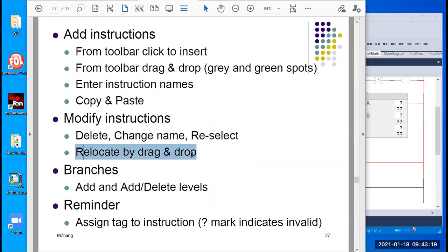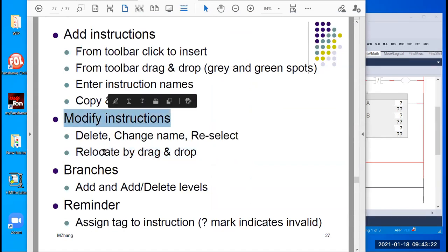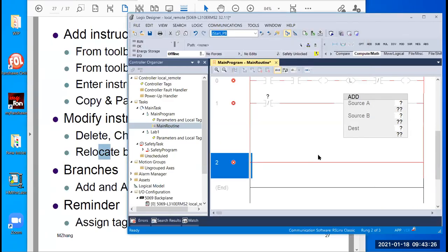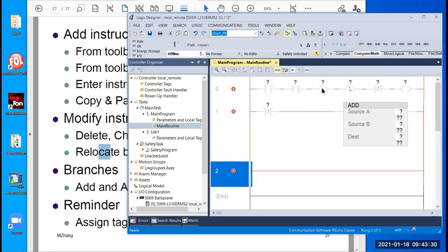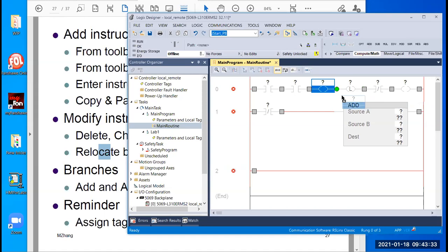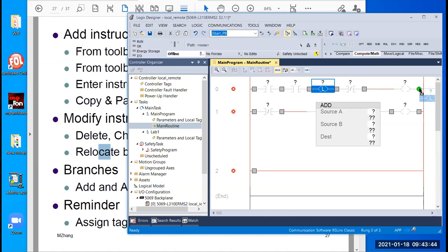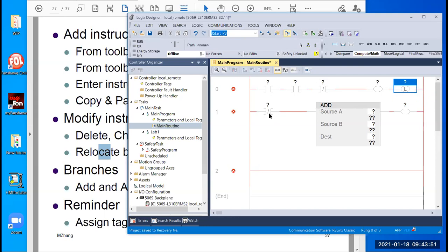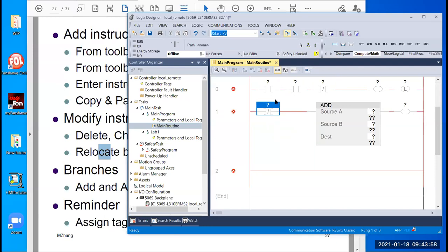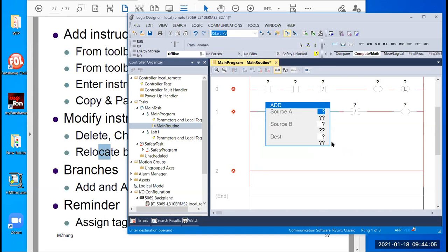You can also relocate instructions — another way to modify. You can relocate by drag and drop. If you want to drag an instruction, you need to click the instruction name itself and then drag it. Pay attention: there are two parts on each element — the instruction and the tag. If you click only the top part you're dragging the tag, not the instruction. You need to click the instruction name to drag the whole instruction.